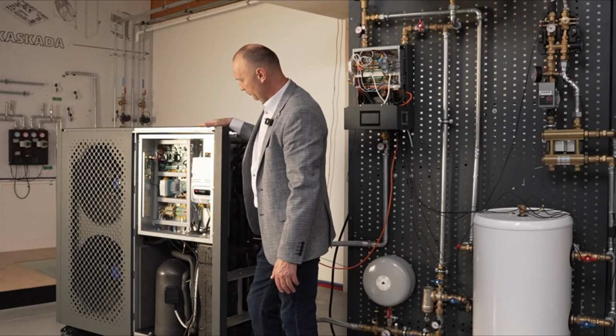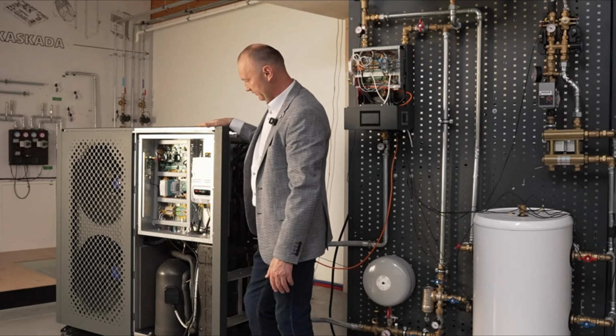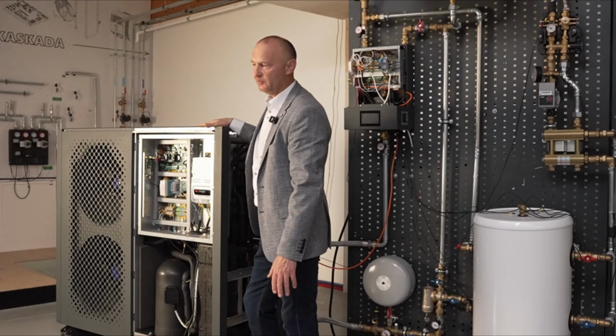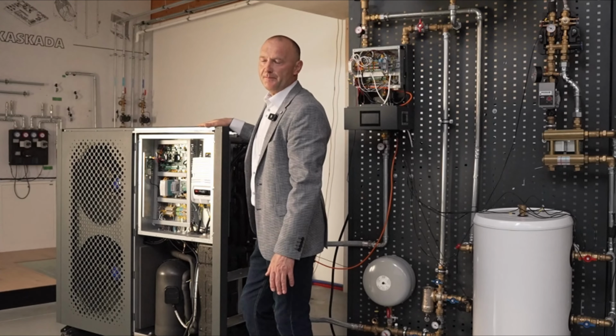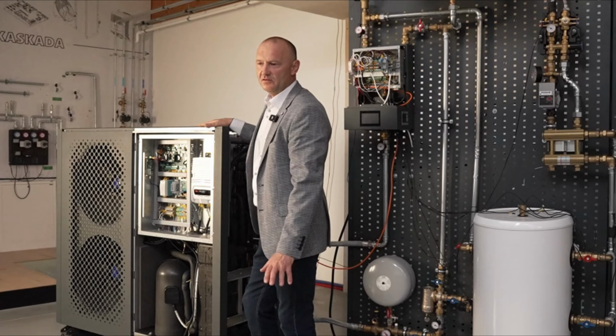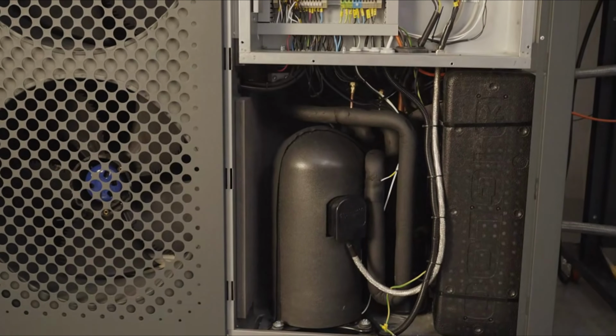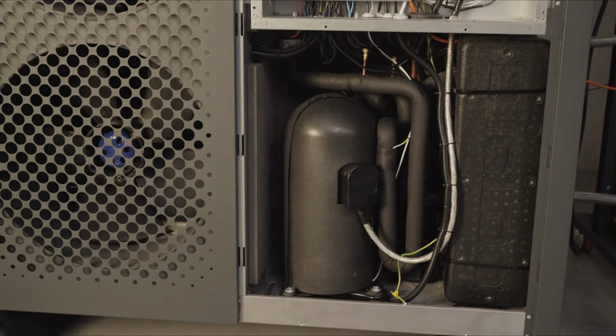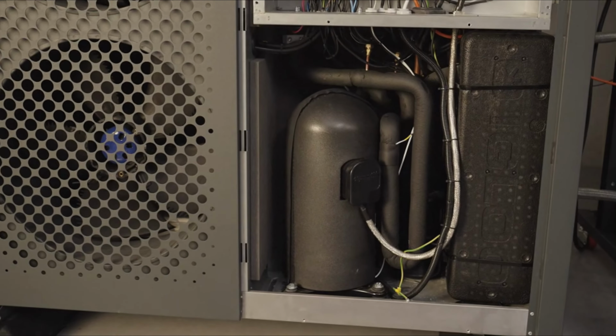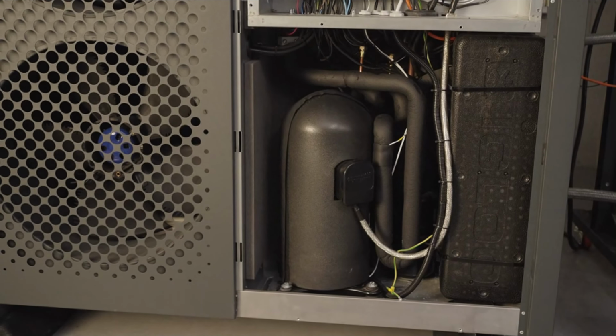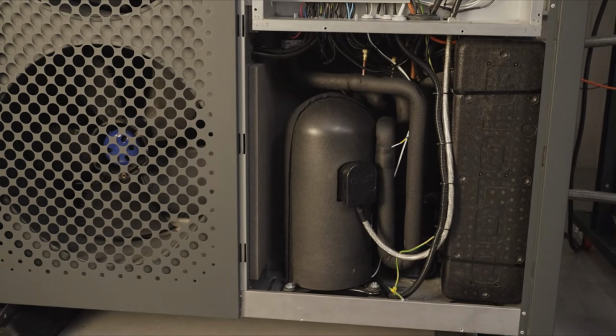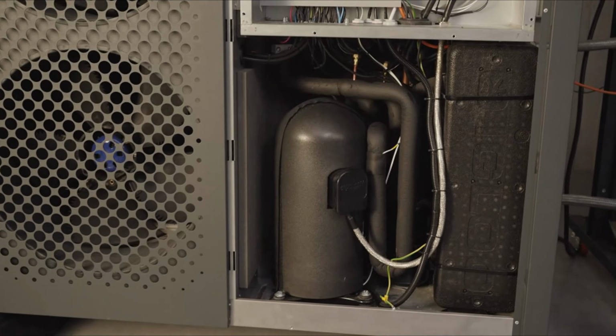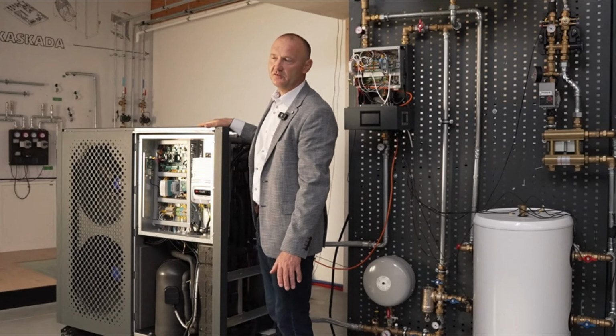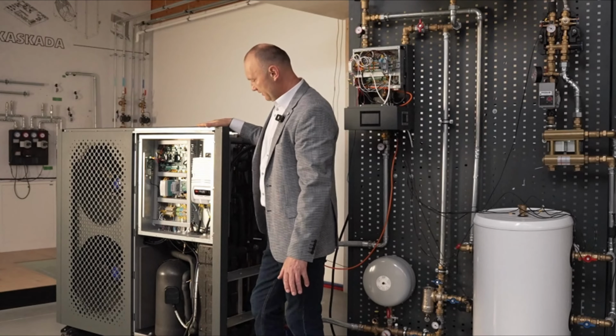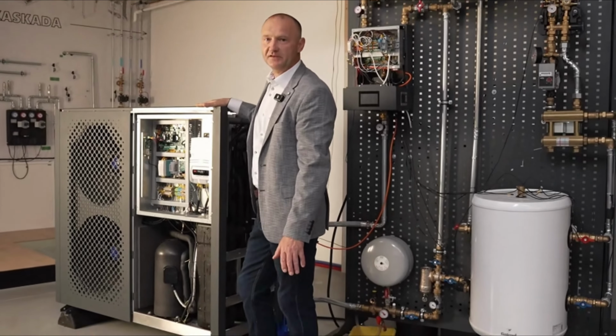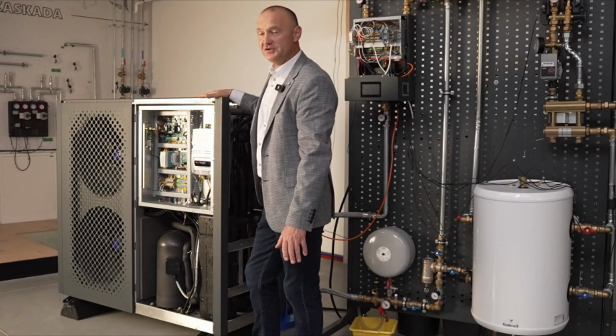This compressor is built in such a way that, because it's a high-speed compressor, it can operate in a range from below 900 to 7,200 revolutions. Therefore, throughout this entire area, it must be fully lubricated, both at 900 RPM and at 7,200. And here, an unusual design was used, although applied by the Japanese for years in many constructions. And that's one of the reasons why we chose this version of the compressor, specifically with pressure lubrication.